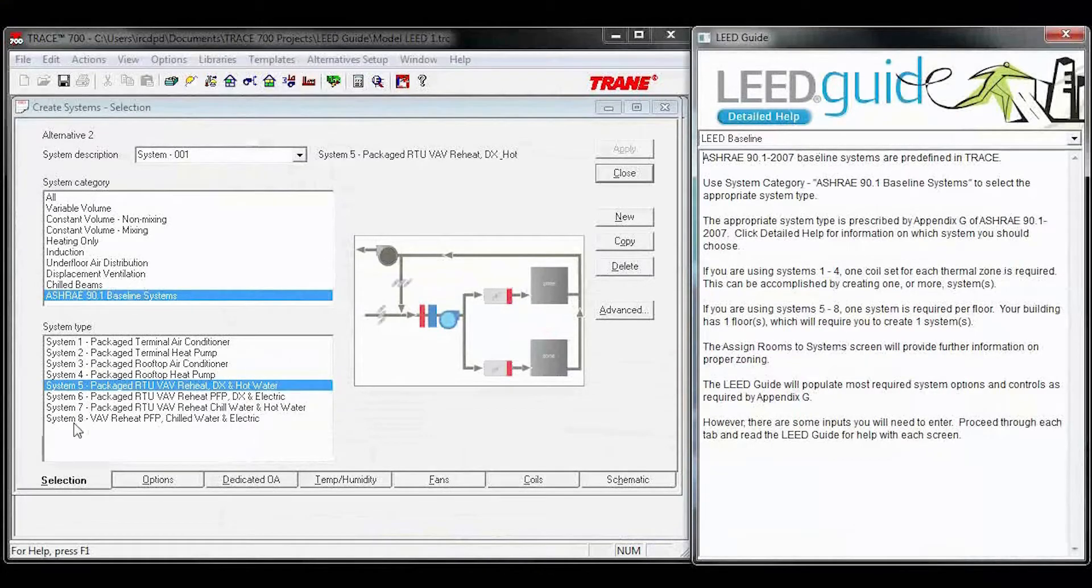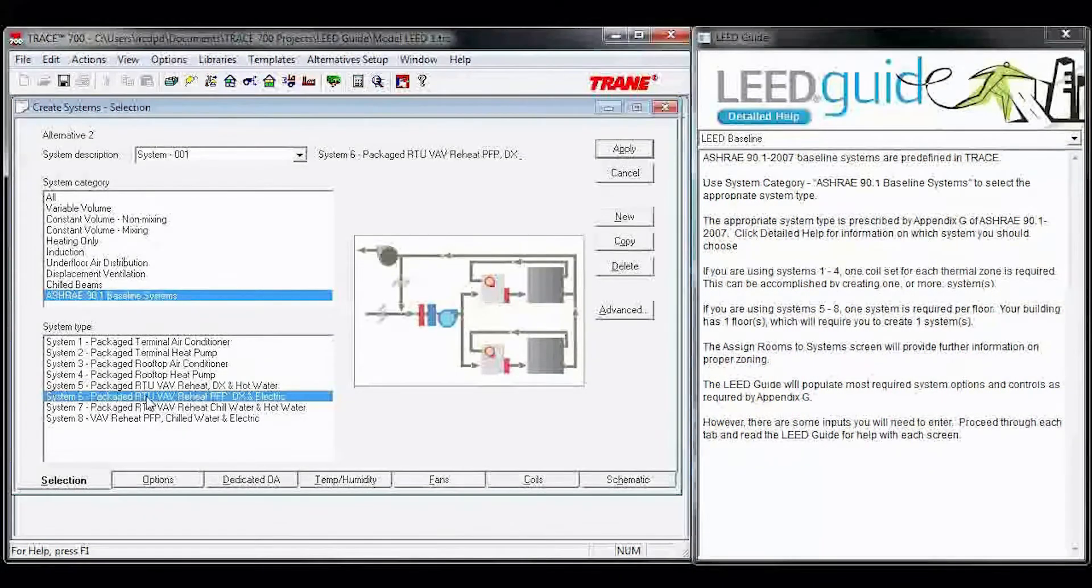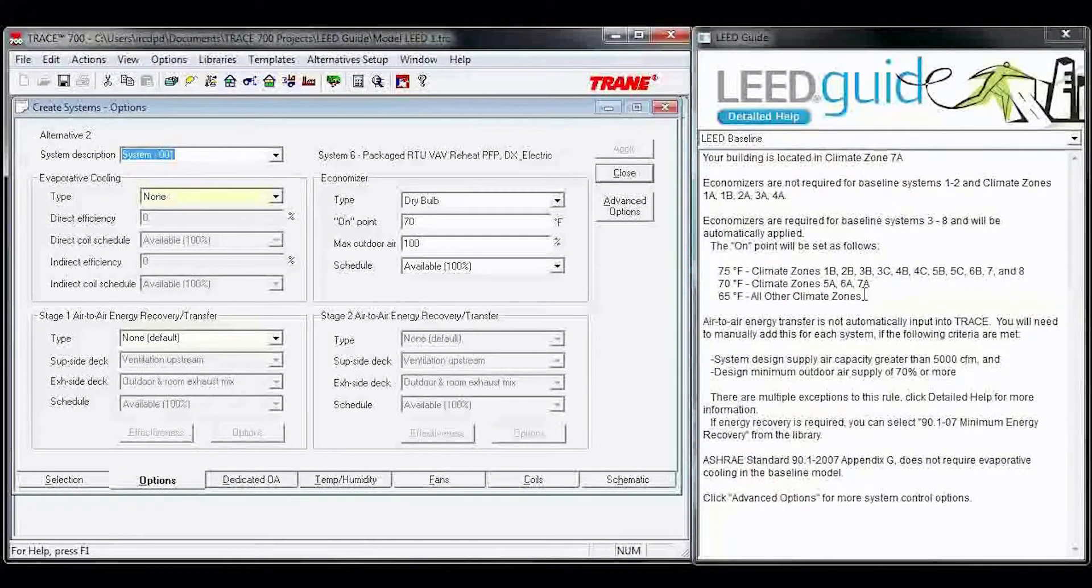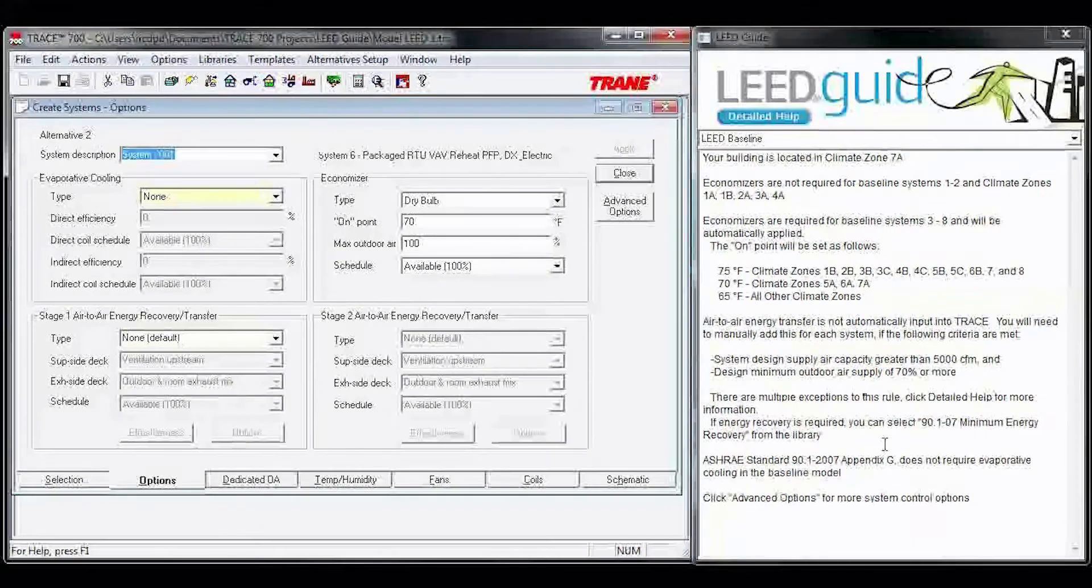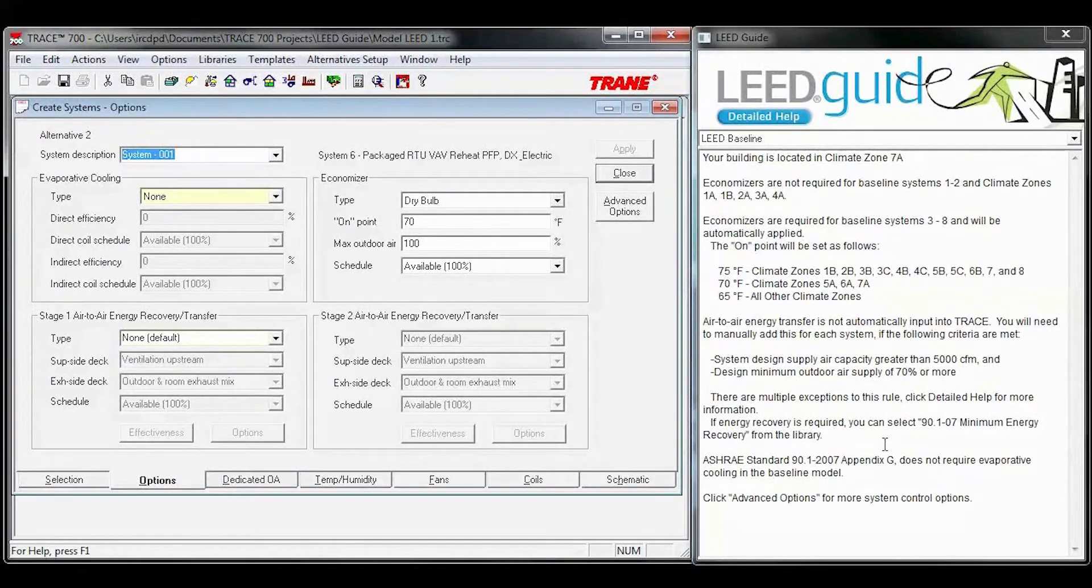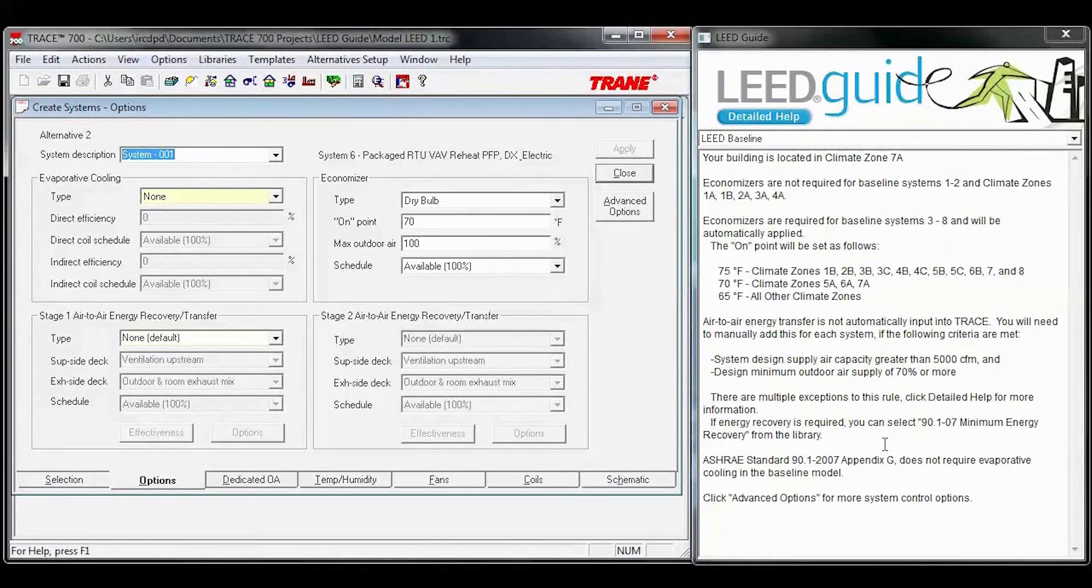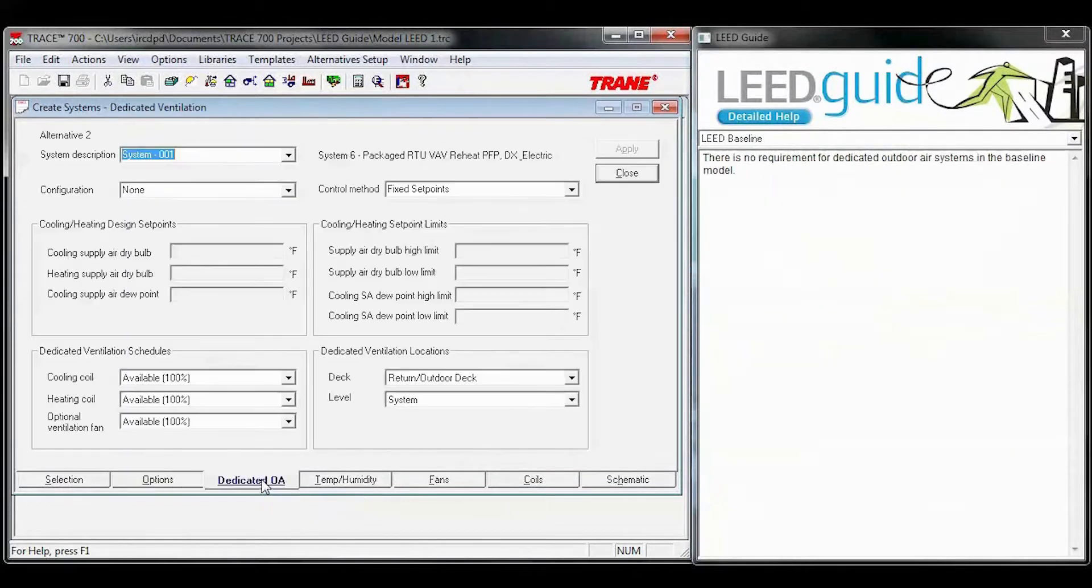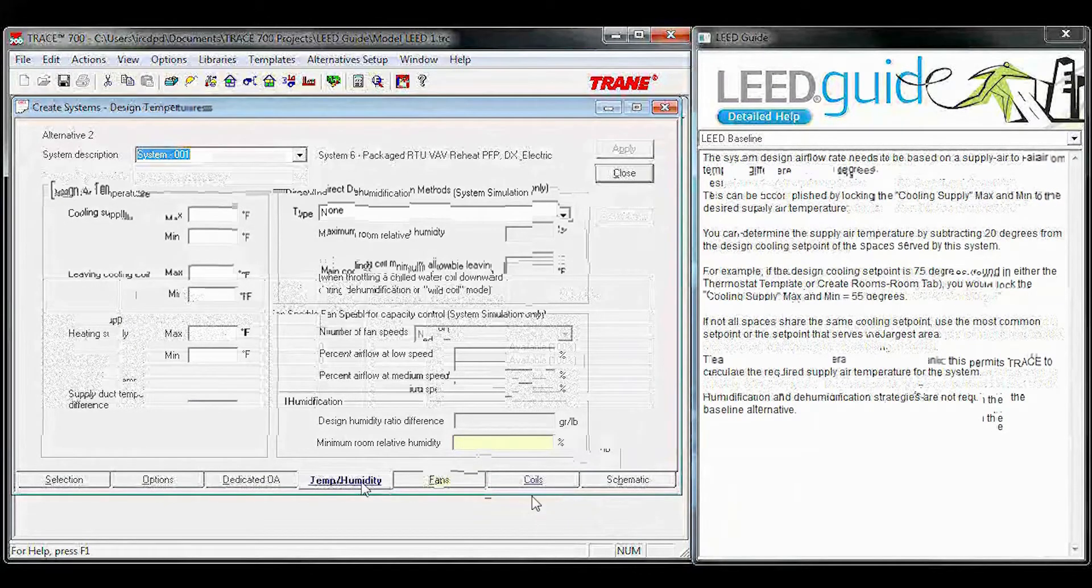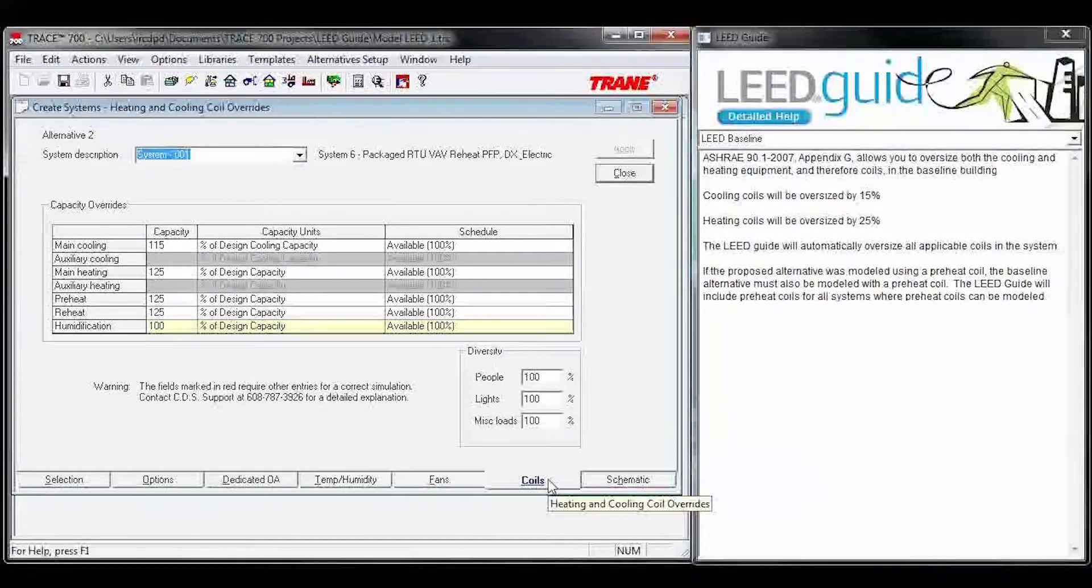Once you have your system, simply click on the system type you need to model. As you step through the different tabs, the LEED guide will let you know what we've auto-populated and what you need to fill in. Things we've auto-populated are Economizer, Optimum Start, Supply Air Temperature Reset, Fans, and Coil Oversizing. As you step through here, you can see the LEED guide updates, lets you know what's going on.